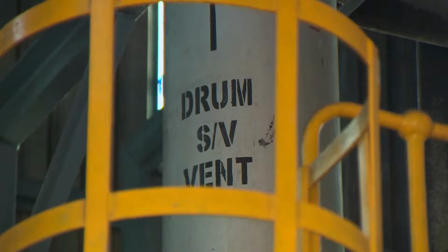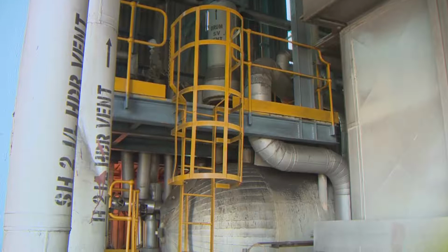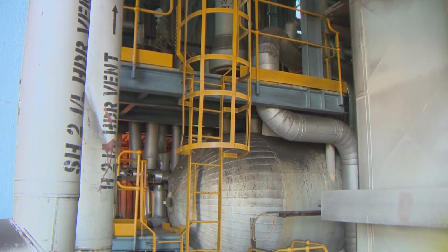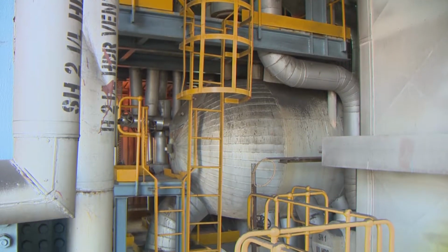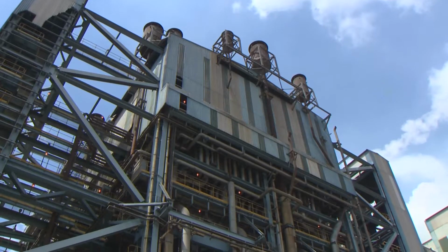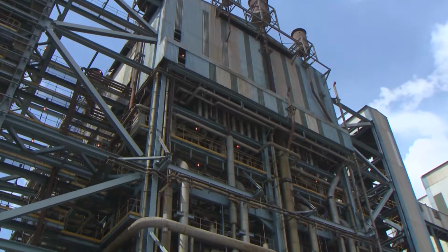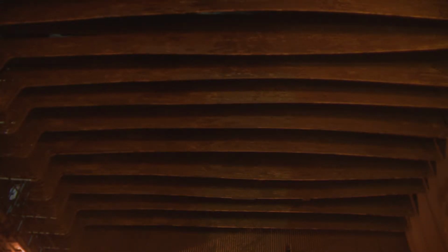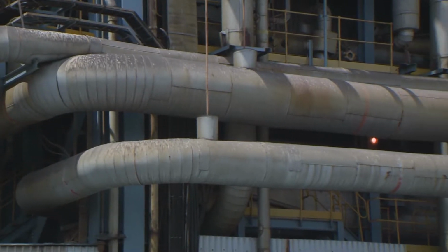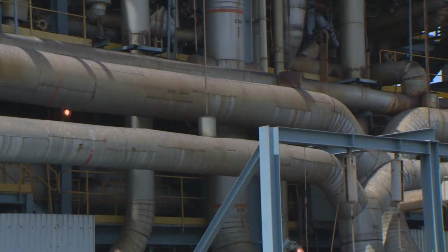superheaters. Required safety valves have been provided in boilers to safeguard the vessel during abnormal pressure rise. The saturated steam passes through 3 stages of superheaters and picks up more heat from flue gas to become superheated steam. The superheated steam is carried by the main steam line to the turbine.